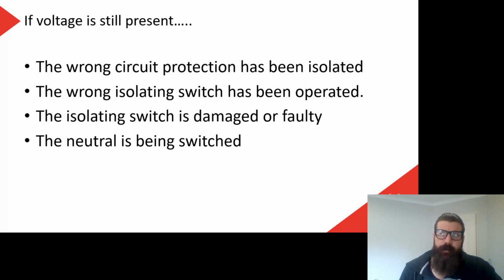If we still find voltage, now this is really important. I've seen people isolate something, test it, find that it's still live, and panic. They don't know what to do next. So if we do switch our circuit breaker or isolating switch off, and then we go back and do our prove, test, prove, and find that circuit's still live, here are the things that we need to check for. Have I switched off the wrong circuit protection, the wrong circuit breaker? Have I switched off the wrong isolating switch? We may have isolating switches there separately from the circuit breaker. That's fine if we isolate a switch rather than a circuit breaker, as long as we can lock it. But the same thing applies. If I've switched off an isolating switch and I've still got voltage, perhaps I've switched off the wrong one. The isolating switch might be damaged or faulty, so I might have physically switched it, but that's not done anything inside the switch. It might be broken.